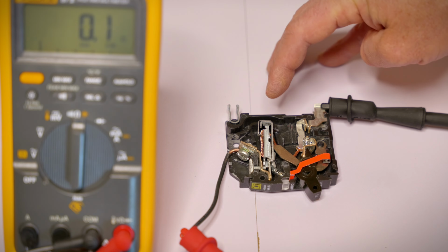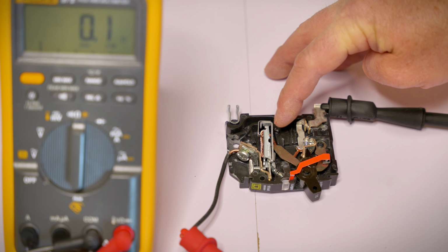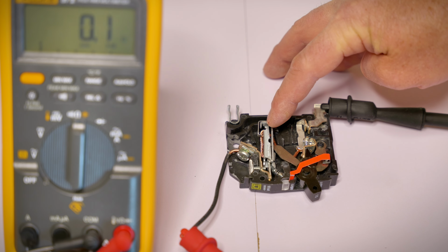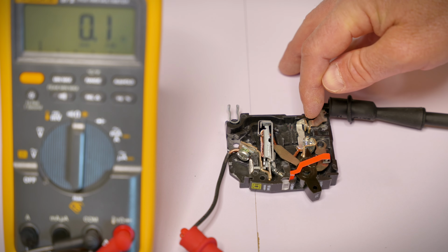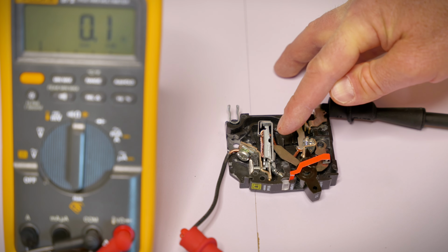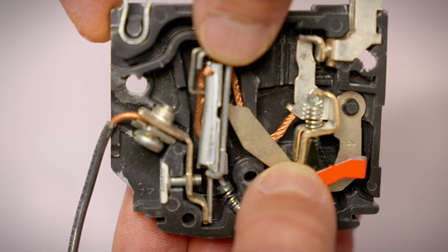Okay, we've gone ahead and reset it, and remember, what's happening is the circuit's heating up and this bimetal strip right here is expanding, and when that expands, it will trip and move this contact arm over. Let's go ahead and watch it in slow motion now.